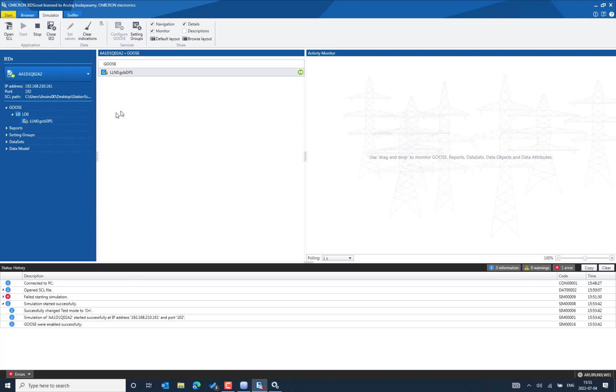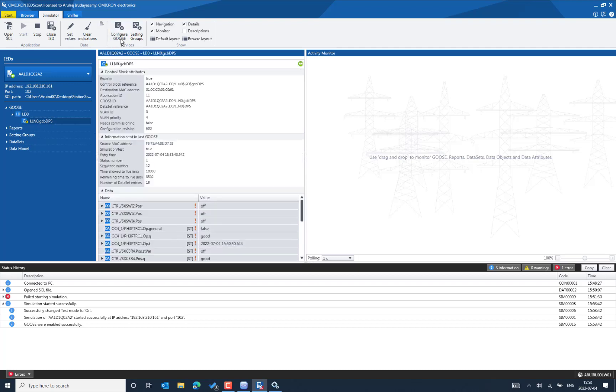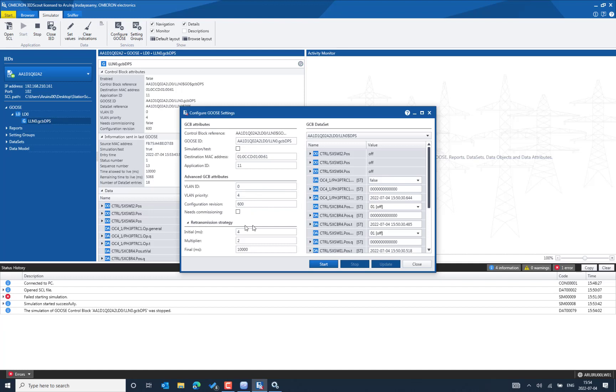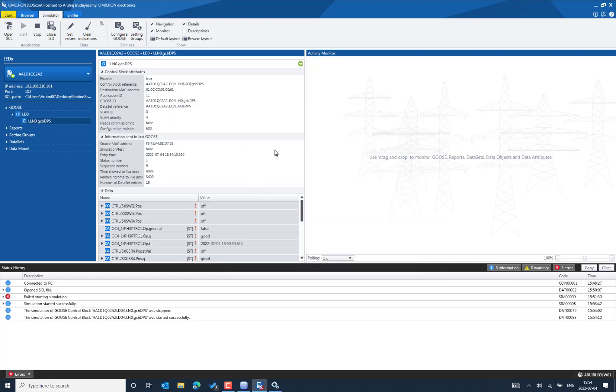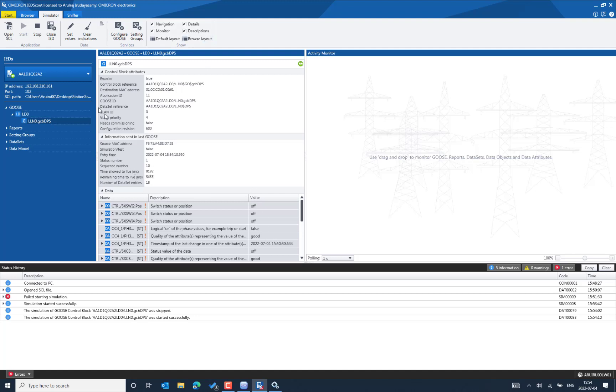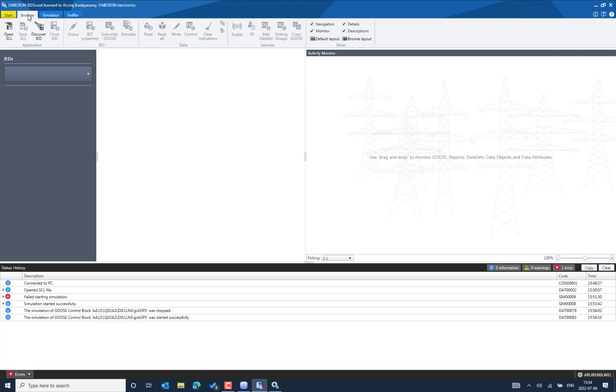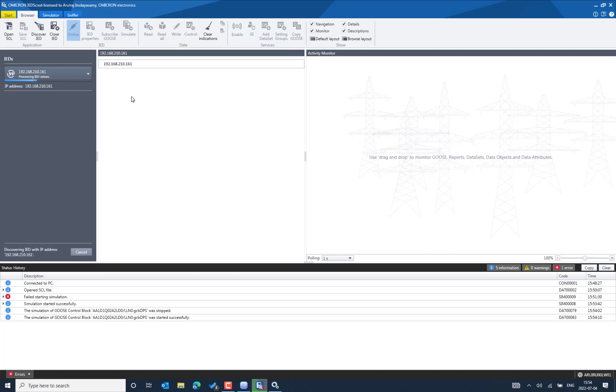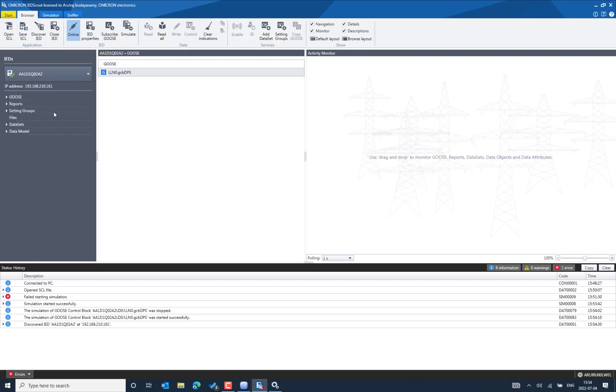The GOOSE control block has been simulated and you can flexibly change the GOOSE control block settings — unchecking the simulation flag, changing the retransmission strategy, and changing the GOOSE message event. You can start publishing without the simulation flag if you are in a test environment, and you can also enable the description. Whatever IED we have simulated, we can discover it from the Browser section. The IED simulated from the Simulator section can also be discovered from the Browser section, because IEDScout can be used as a simulator and client application simultaneously.